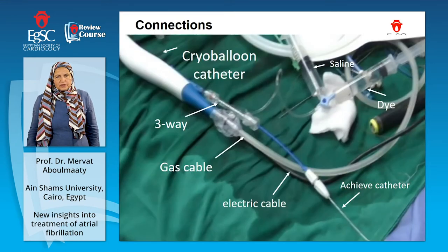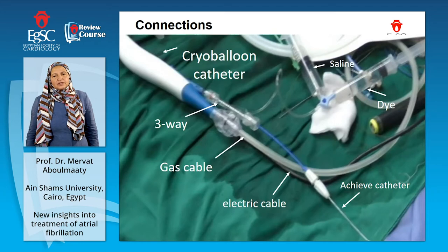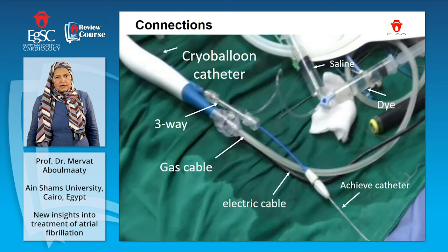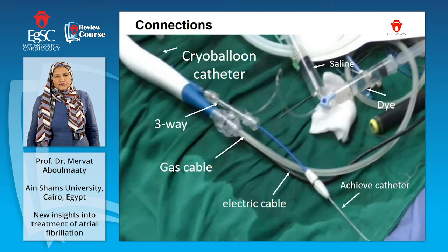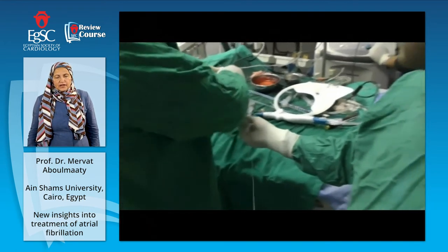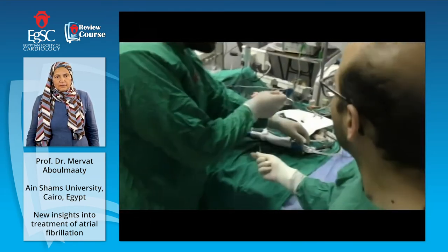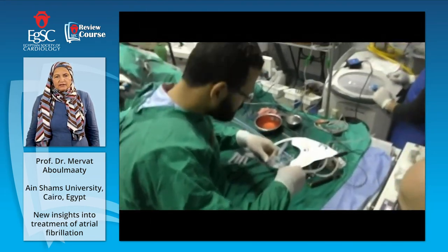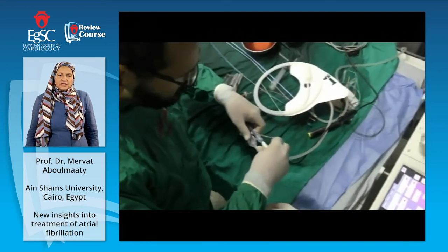We started to prepare the machine and equipment for the cryoballoon ablation. This is the cryocatheter with a sideway to inject saline and contrast. Here is the Achieve catheter, which records the pulmonary vein potentials. The gas cable is connected to the machine, which delivers the gas that makes the cooling, and the electrical cable connects to the machine. Everything should be flushed with heparin, everything should be checked. Here is our team: Dr. Omar Hatem, Dr. Musa, and Dr. Mazen.